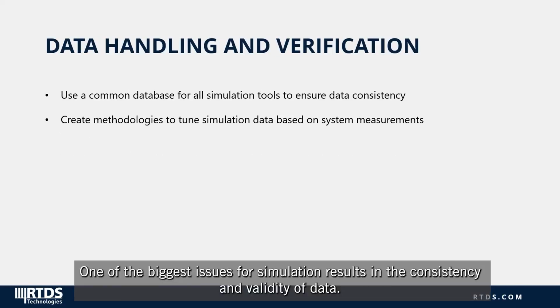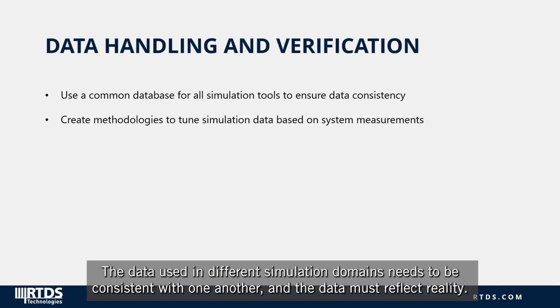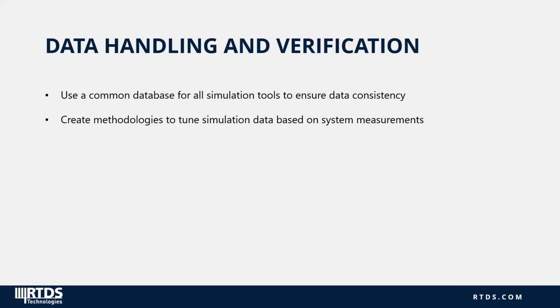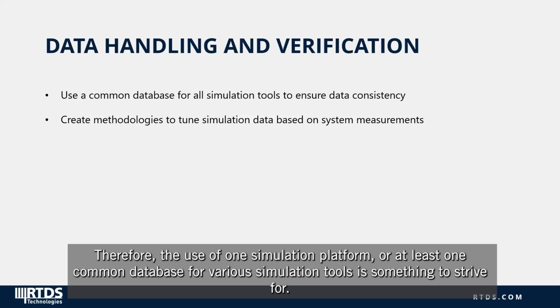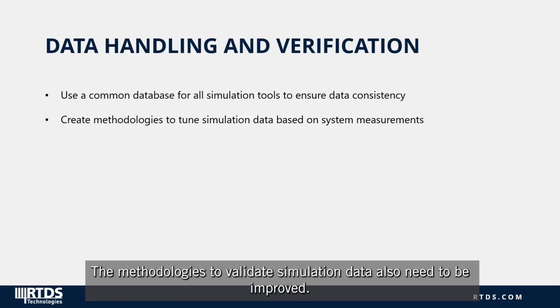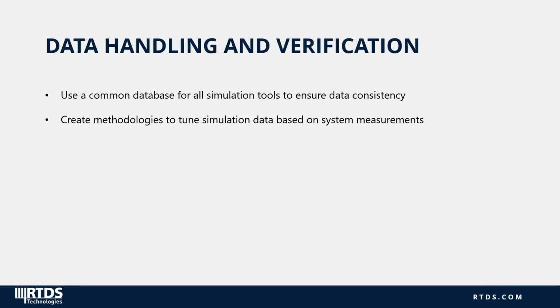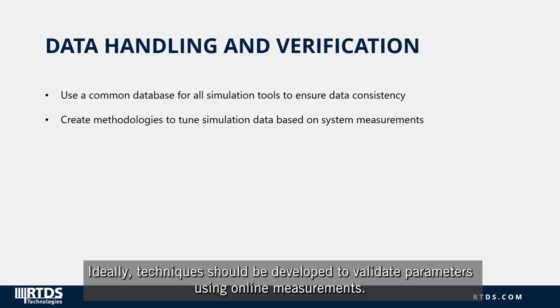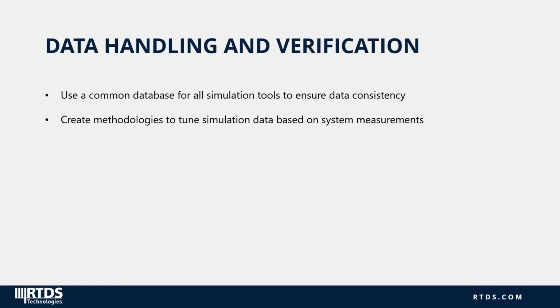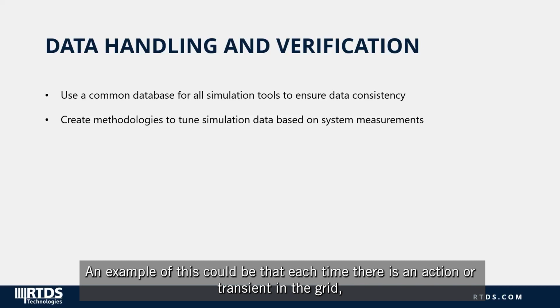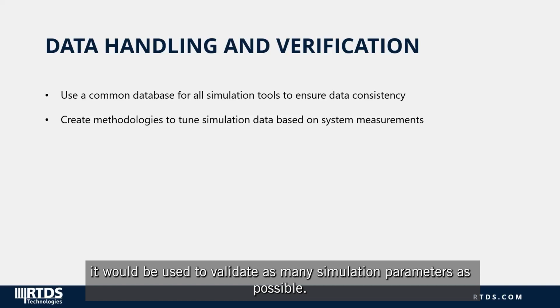One of the biggest issues for simulation results is the consistency and validity of data. The data used in different simulation domains needs to be consistent with one another, and the data must reflect reality. Therefore, the use of one simulation platform, or at least one common database for various simulation tools, is something to strive for. The methodologies to validate simulation data also need to be improved. Ideally, techniques should be developed to validate parameters using online measurements. An example of this could be that each time there is an action or transient in the grid, it would be used to validate as many simulation parameters as possible.